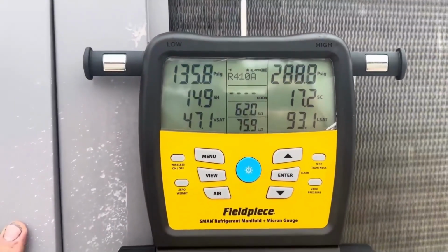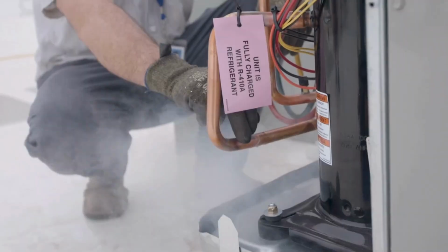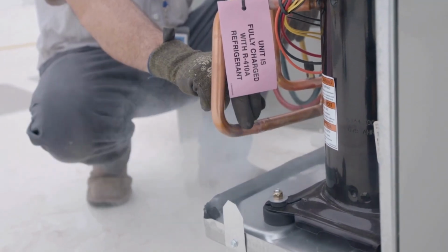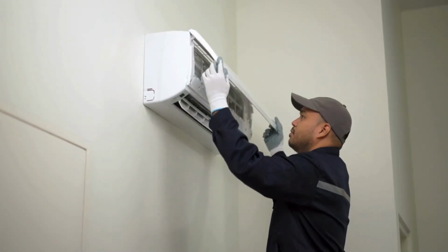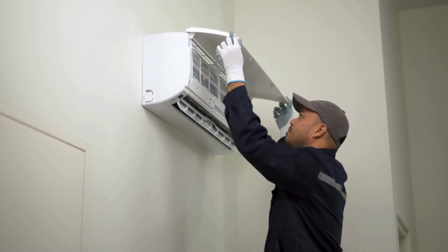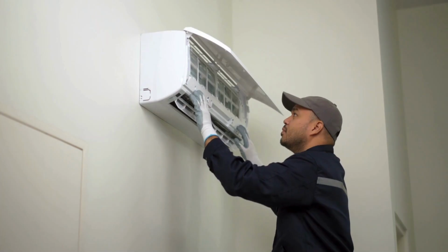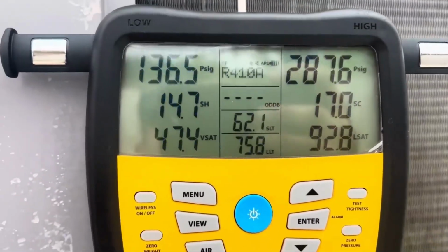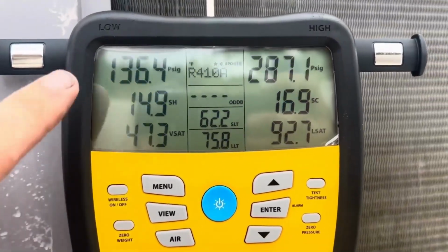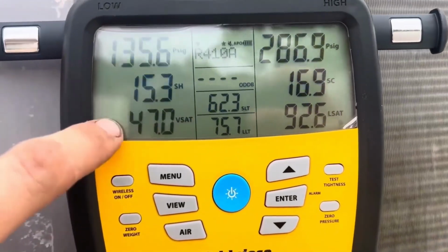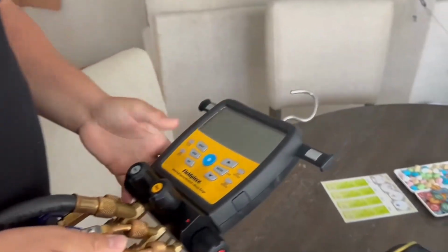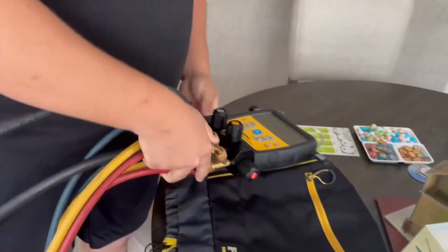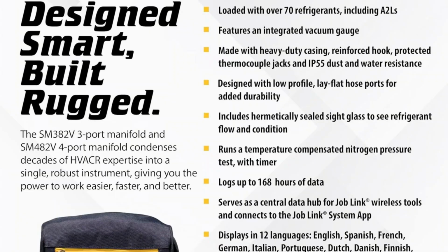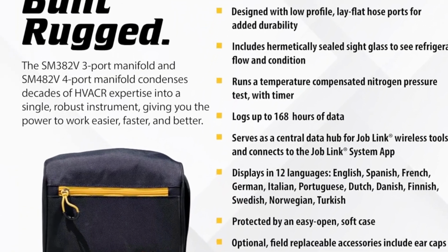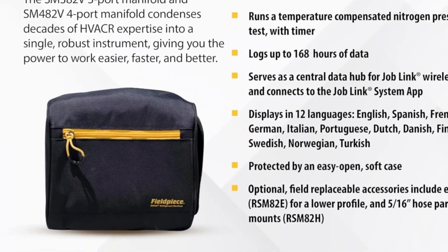Clear and readable display under different lighting conditions. Visibility is something that many technicians underestimate until they're out in the field under bright, direct sunlight or in dimly lit technical rooms with poor lighting. This model keeps the readings clearly visible without glare or the need to get close to the manifold. It doesn't feel like a delicate or fragile device. The durable casing and buttons are designed to withstand light impacts, vibrations, or continuous daily wear and tear, making it an ideal choice for technicians who are frequently on the move.